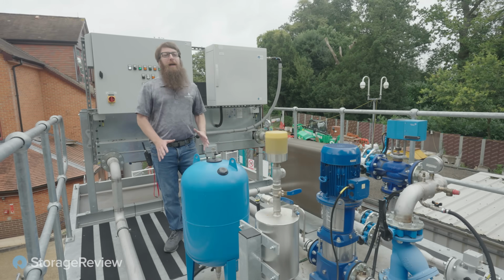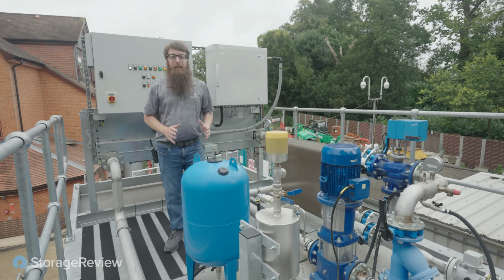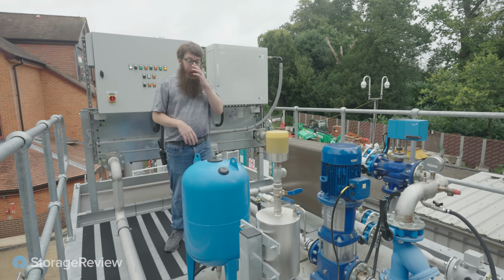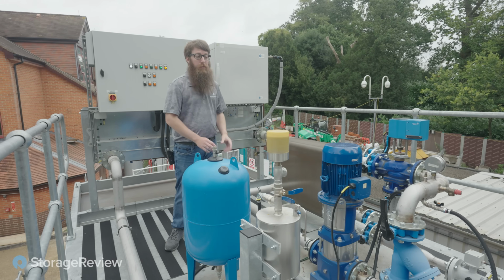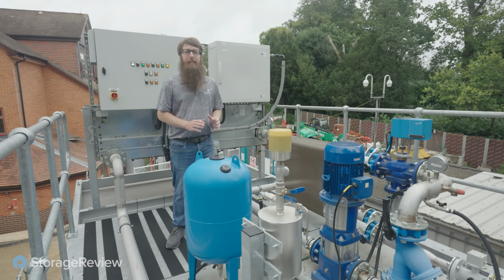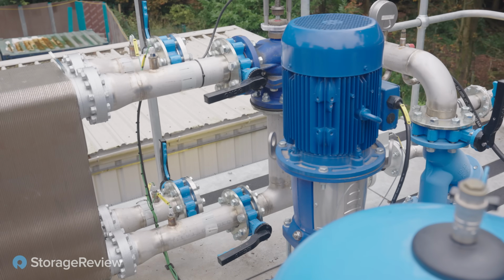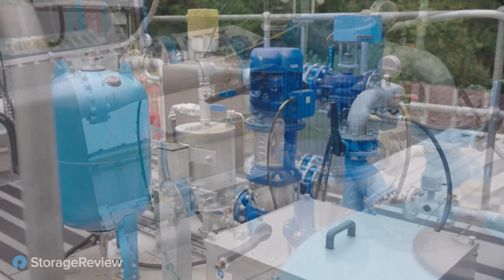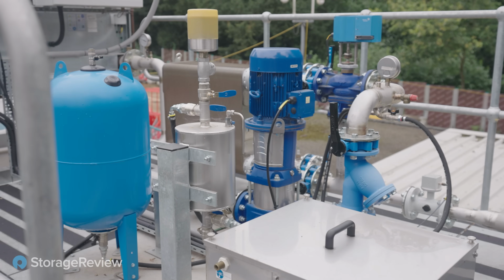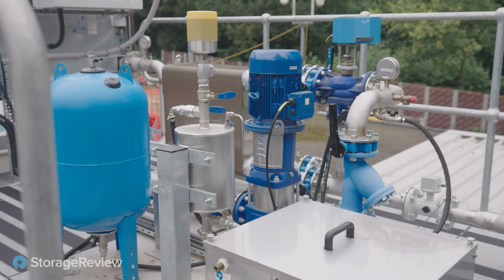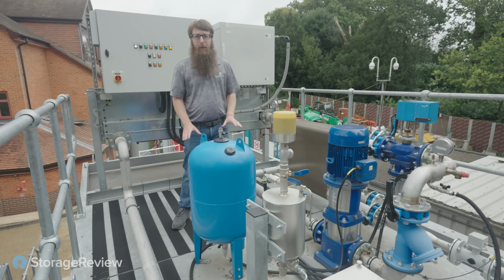Out here on the roof of the Megapod, we can see where all of that heat ends up going. There's a couple of options they can do with the heat that comes out of those systems. Remember, this isn't the fluid that's in the tank down there—running through these pipes is a glycol mixture that interacts with the CDU heat exchangers inside the SmartPods. So up here, we've got a couple of different ways to deal with the heat.